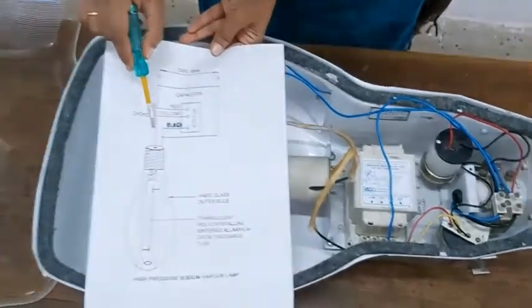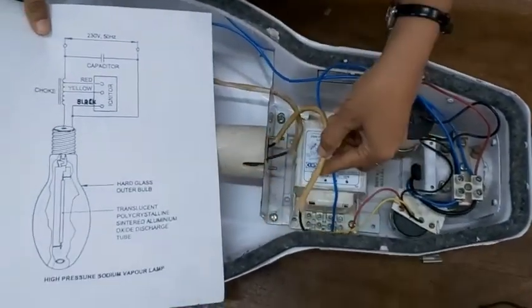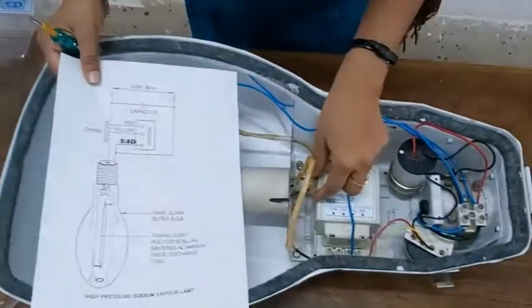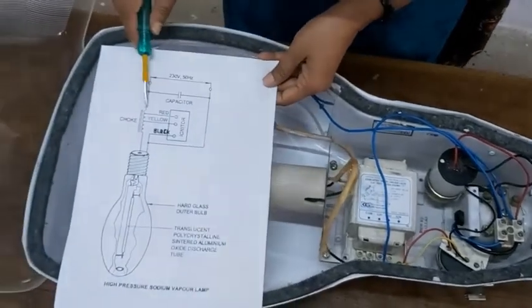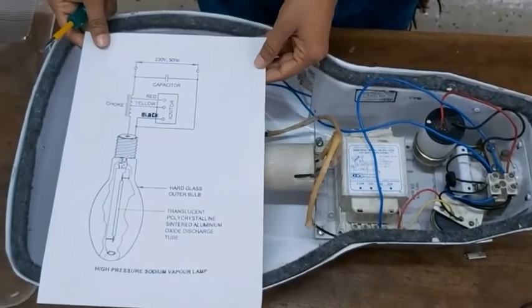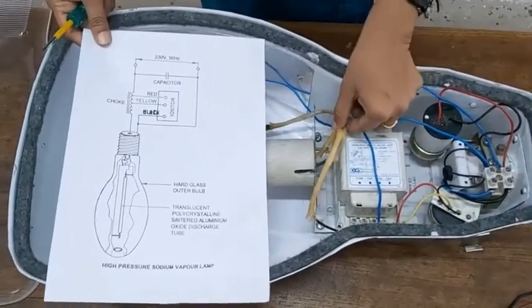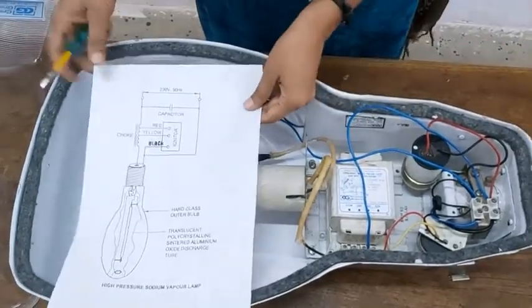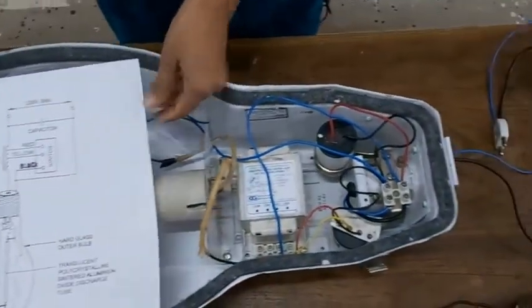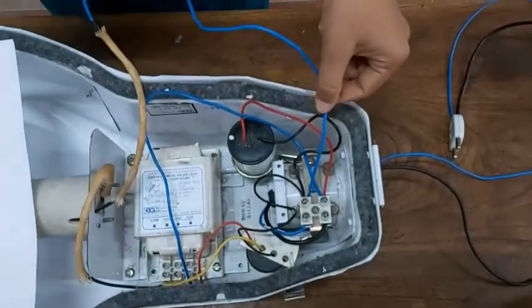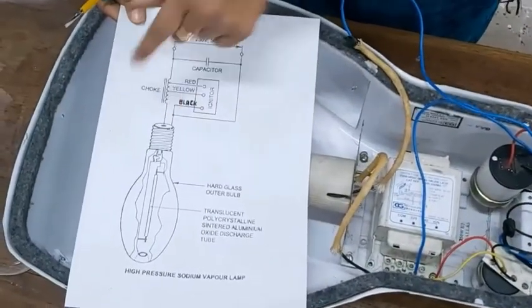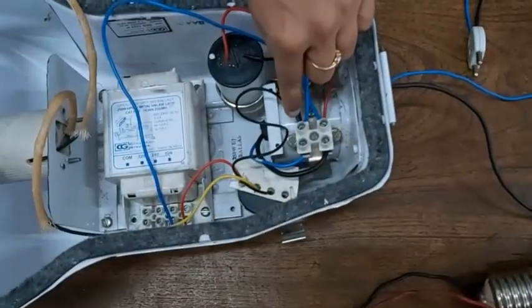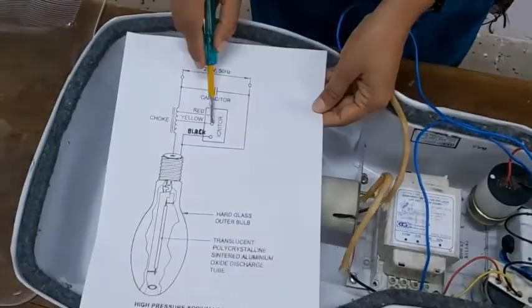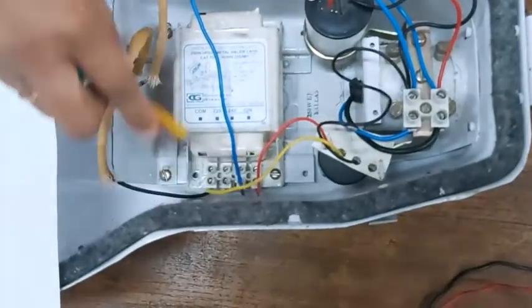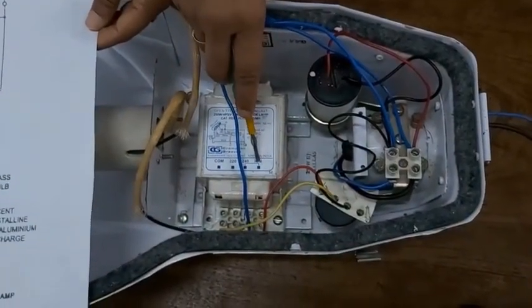Then the other end of the choke, that is this common, is connected to the lamp holder. The other wire from the lamp holder is connected to neutral of the supply. To this, the black wire from the igniter is connected. So this black wire of the igniter is connected to neutral of the supply. The yellow wire from the igniter is connected to 220 volt. The red wire from the igniter is connected to the igniter terminal of the choke.